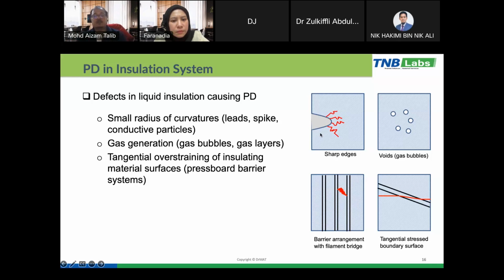So these are the possible factors that can cause partial discharge activity in liquid insulation. When we have sharp edges, the sharp area causes more stress, and it will create partial discharge. Second, when we have a gas bubble or air bubble, it can also create partial discharge, because the bubble has a dielectric strength less than the entire insulation system. Also, when we have a bridge between two conductors in the liquid. The other possible cause is tangential stress at the boundary surface.